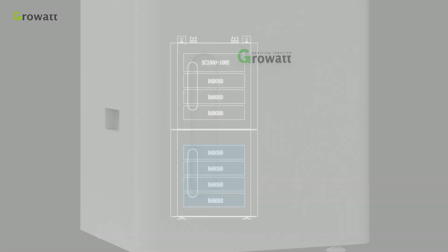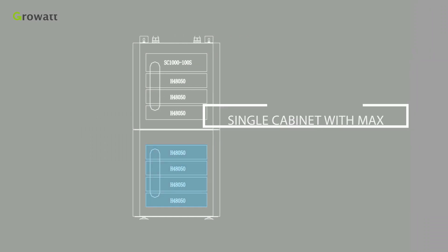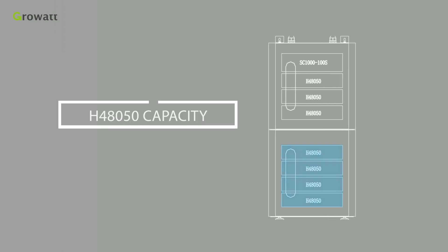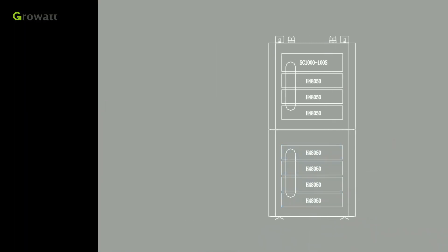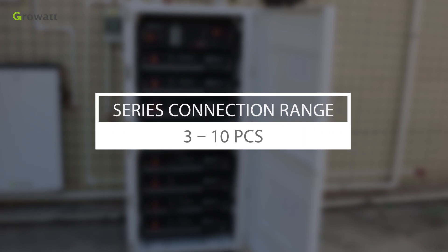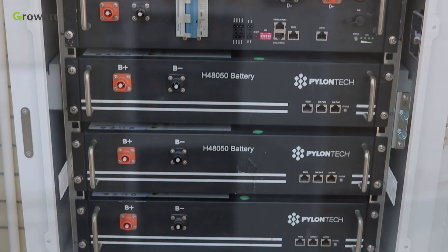There are 6 models in SPH series. A single High Voltage Battery Cabinet can be installed with a maximum of 4 pieces of H48050 battery modules. Each battery module is 2.4 kWh, and the range of battery series connection is from 3 pieces, with battery cabinets stackable to reach a capacity range from 7.2 kWh to 24 kWh.